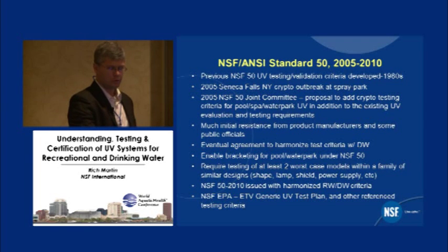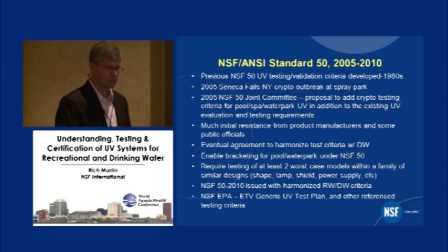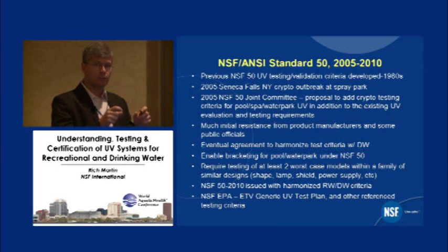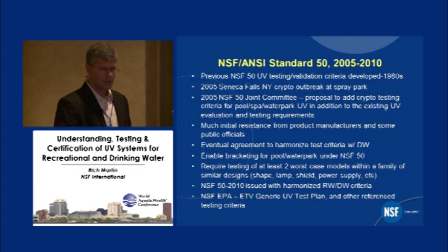So after a few years, we found that the Joint Committee, or the oversight group over Standard 50, said, yes, we should put this in, not make it a requirement for all things, but make it a requirement if you want to make a claim about crypto inactivation. So again, a very reasonable approach. And then part of that approach was to require testing of at least 2 worst-case models of a similar family. And I'll get into those types of details next.